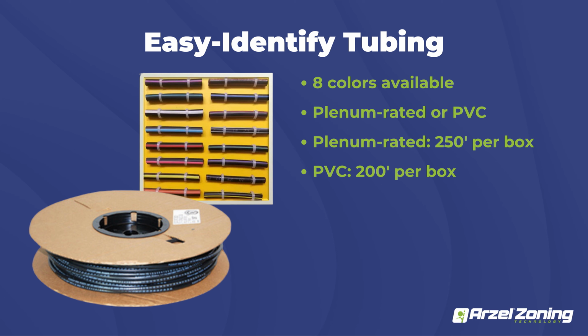And it does come in 8 different colors. Like I mentioned before with the AirBoss, it goes up to 8 zones. That's the largest panel that we offer. So we essentially offer a color per zone. And it just makes it easier to identify if someone goes back to troubleshoot the system. They can look at the tubing color and figure out exactly what dampers are on what individual zone on that panel. So it just makes it easier to troubleshoot.